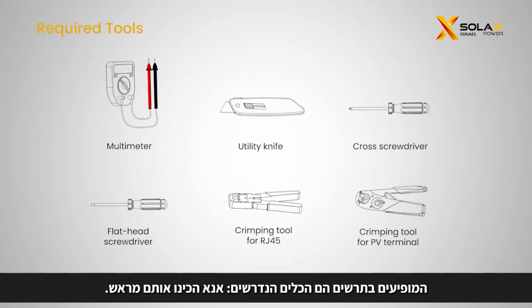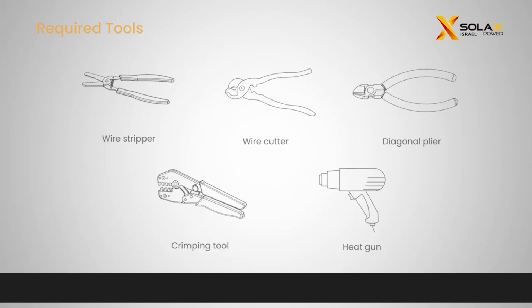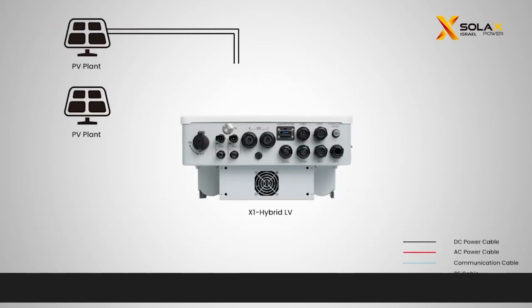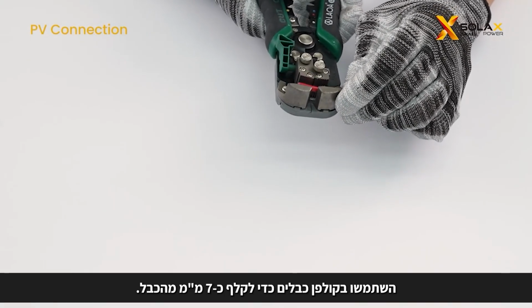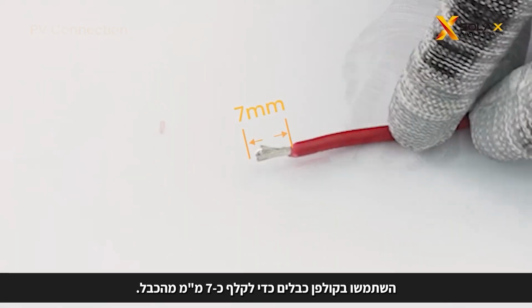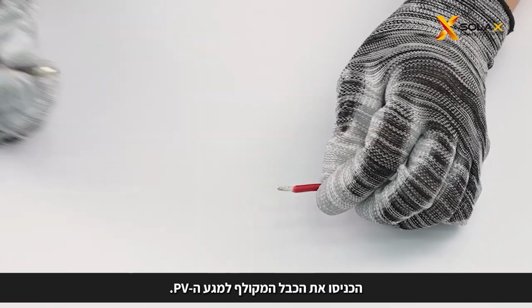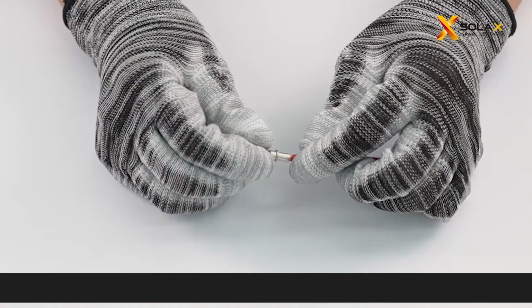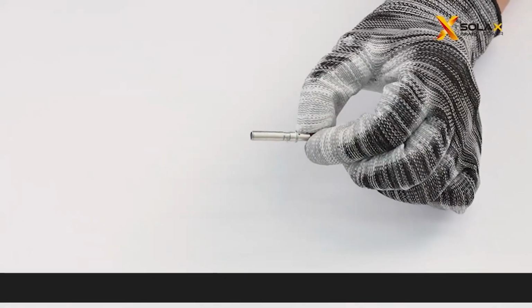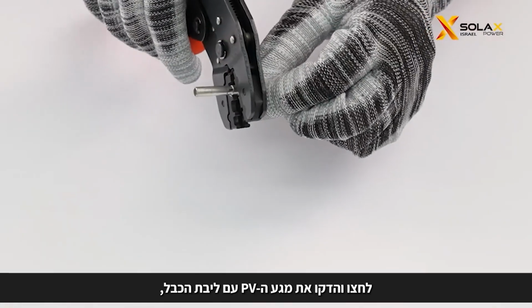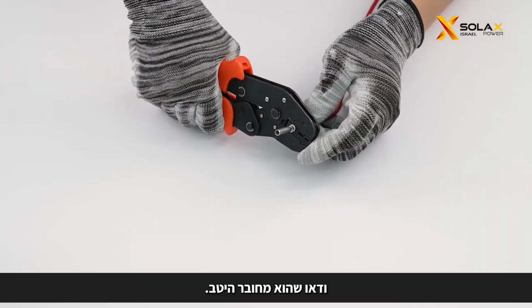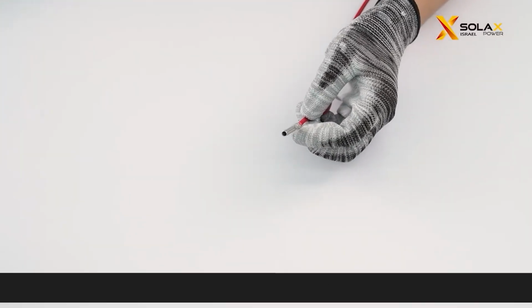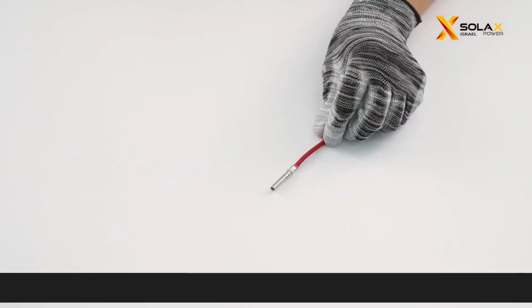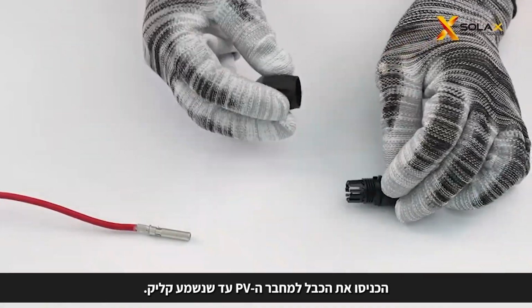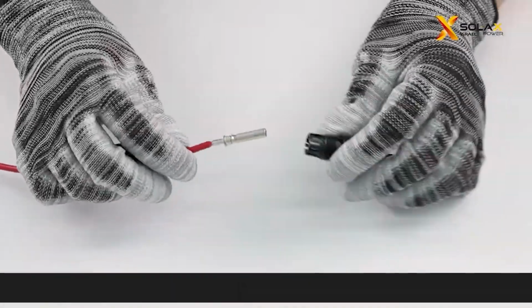Following are some required tools, please prepare them. Use a wire stripper to strip approximately 7 millimeters of the cable. Insert the stripped cable into the PV pin contact. Press and tighten the PV pin contact with the cable core, make sure it is firmly connected. Insert the cable into the PV connector until a click is heard.